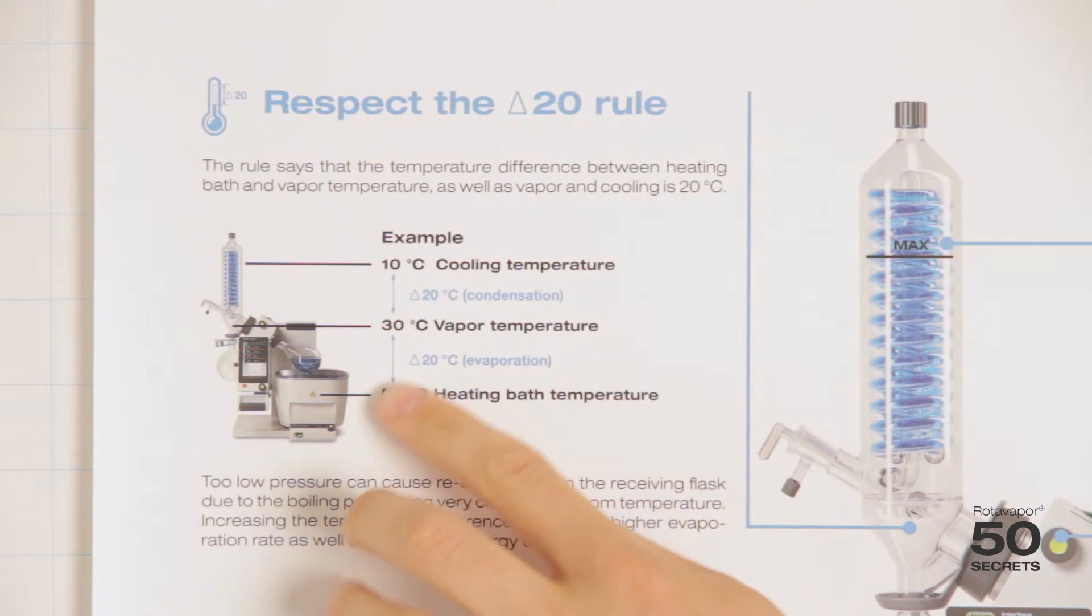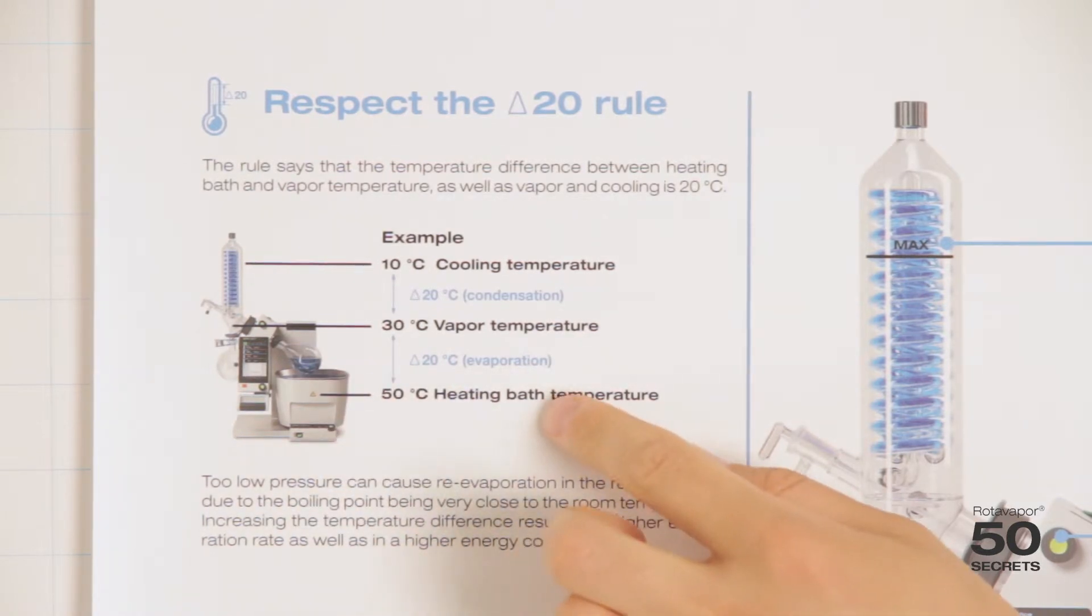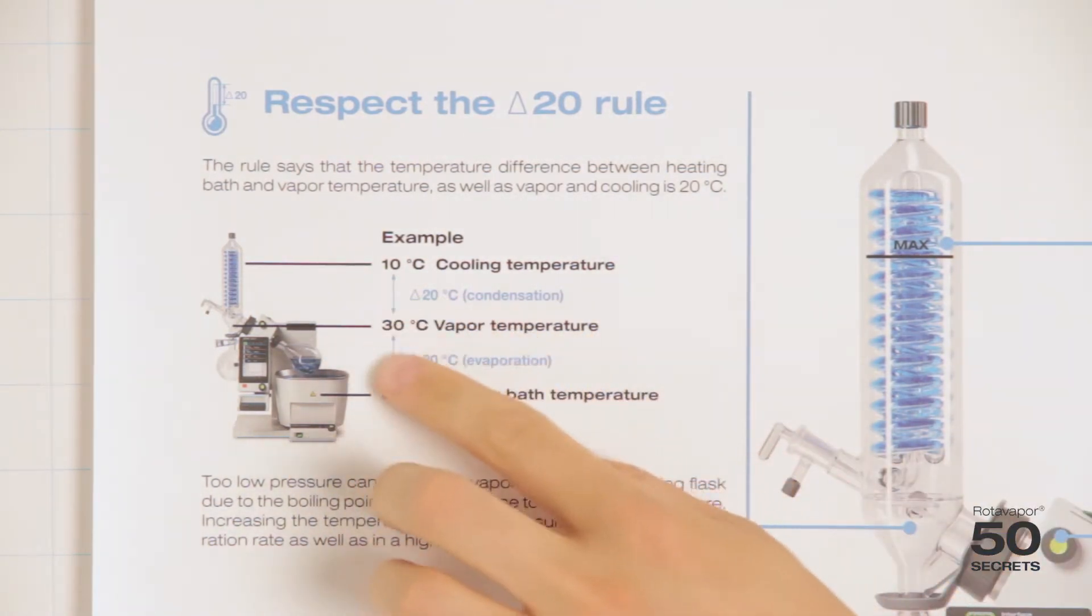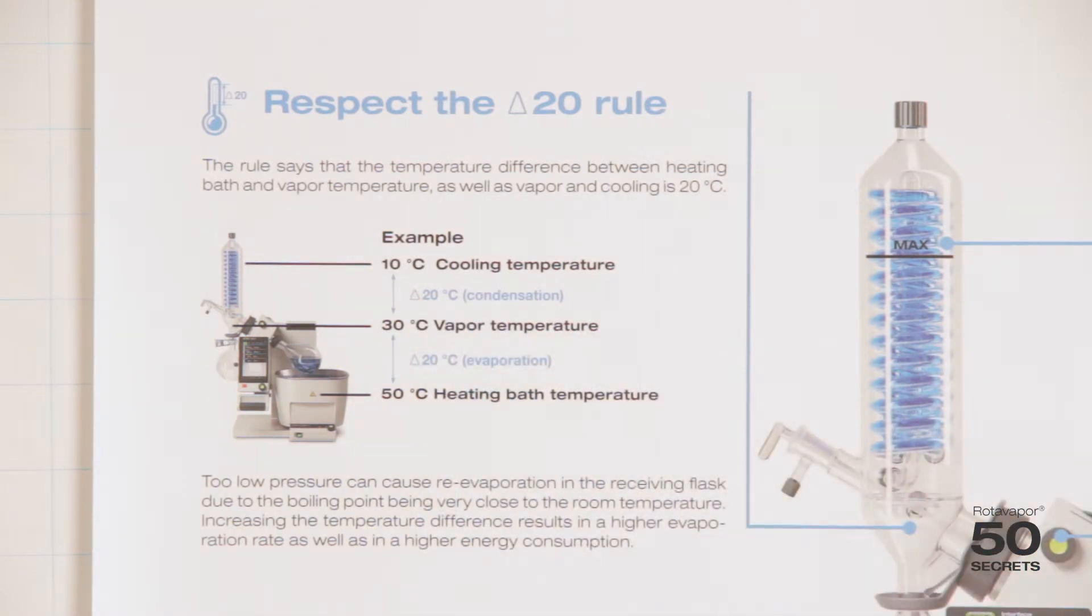As an example, we start with 50 degrees heating bath temperature, 30 degrees vapor temperature, and 10 degrees cooling temperature. The rule of thumb is usually that you try to adjust the vapor temperature to whatever is needed.